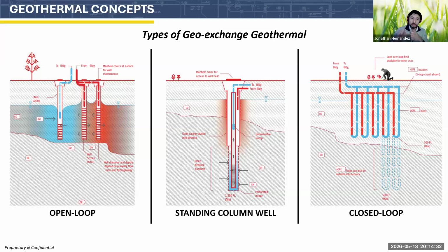Fast forward to one drilling operation of a concentric standing column well. What this does is turn one drilled well into both a production and an injector, using the annular space as the injector from the building—you see the red arrows from the building—and then the blue electric submersible pump within the inner diameter column recovers that fluid, that water that has been exposed to the rock, either releasing or exchanging heat by recovering it.